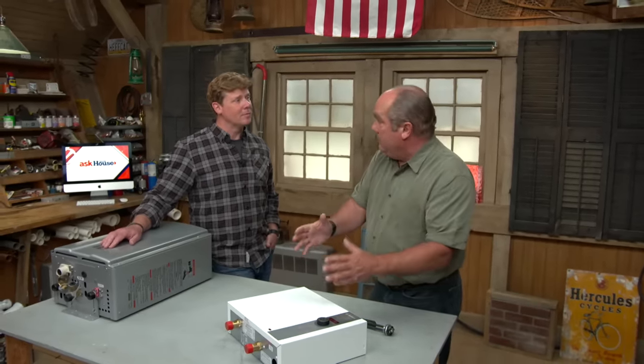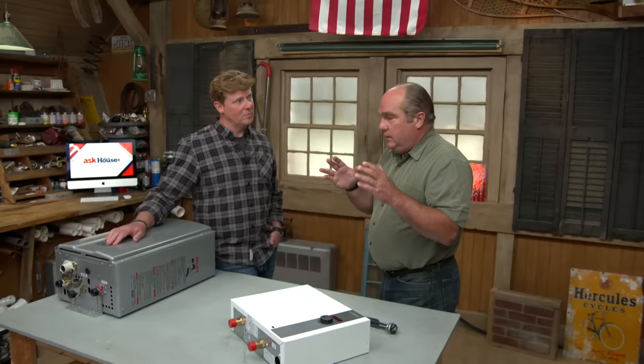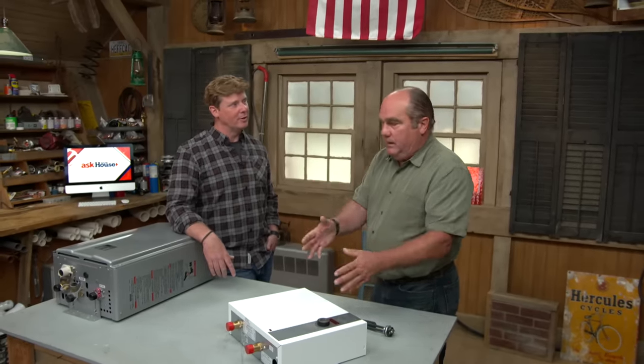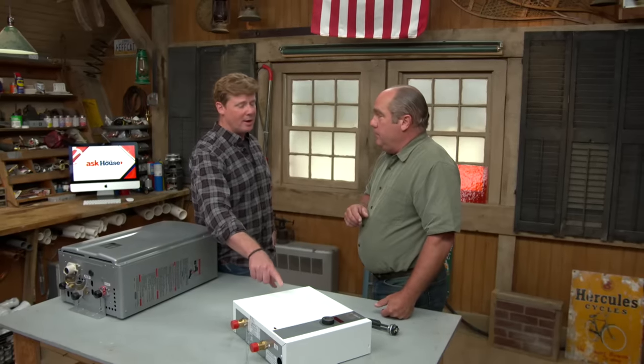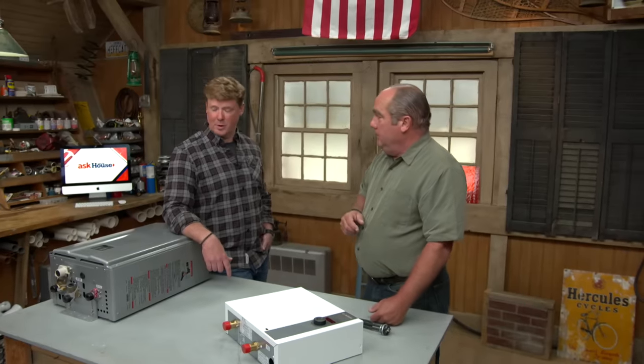If you're trying to heat very cold groundwater, you need plenty of power. A unit like this in New England could give you about 2 to 2.2 gallons per minute — right at the threshold of one shower. That's not really viable for a house with two or three bathrooms and a family. It could work in an in-law suite or an ancillary building. Down in Texas, this could potentially work for the whole house all day, as long as you have enough available power.